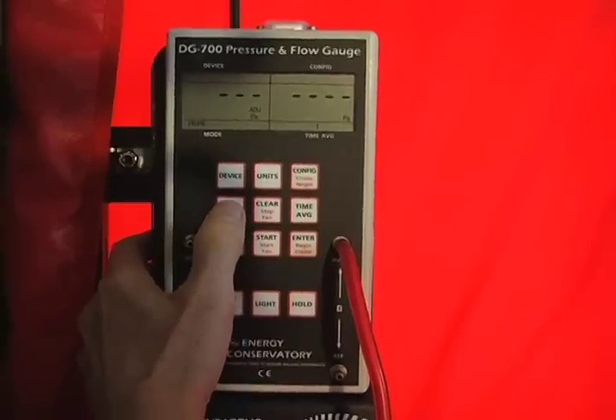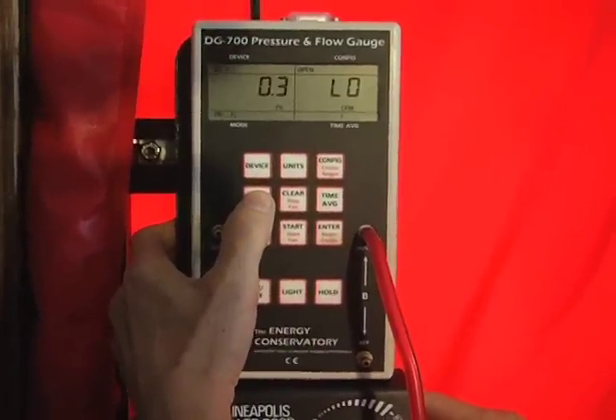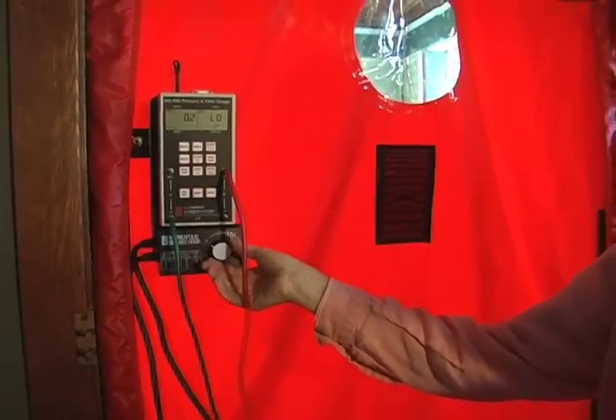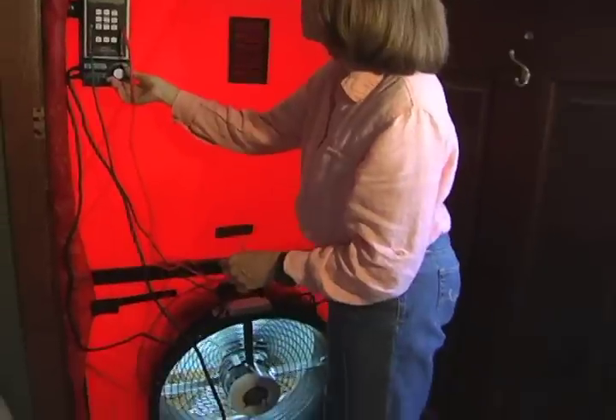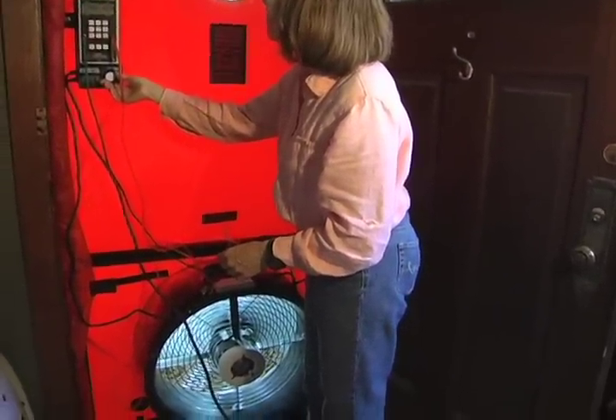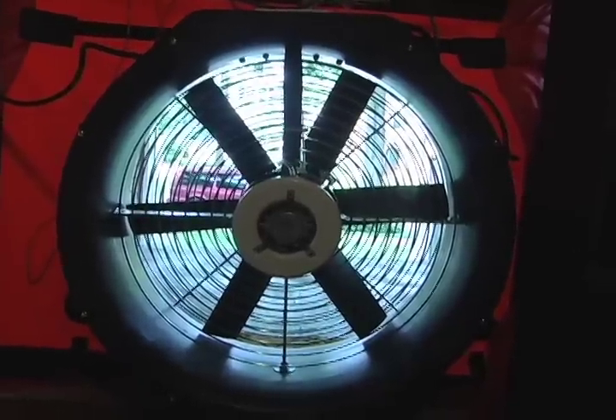In order to measure how leaky a home is and to find leaks, we use the blower door and airflow meter. The blower door is the most important tool we have for diagnosing air leaks and measuring the absolute leakage of a home. Also, without the blower door, we don't know how tight the house is after improvements. The airflow meter, also called a manometer, is attached on one side of the meter to the fan. The other side measures the pressure created by the fan.